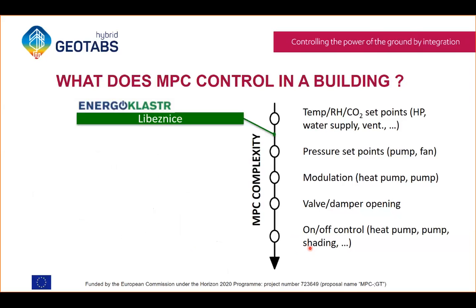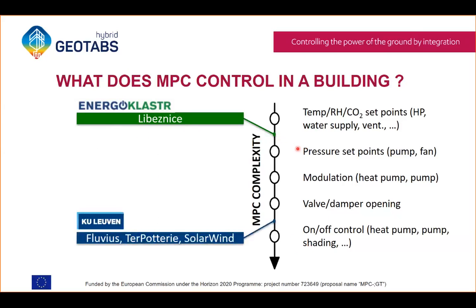Looking at the different MPCs developed in the project, there were two types. The first was developed by Energo Klastr for the school in Libeznice, where they sent set points for the HVAC, including temperature set points and pressure set points for the fans, as they included CO2 concentration. The second type of MPC, developed by KU Leuven for three buildings, used a much more complex model and could control up to the valve level.